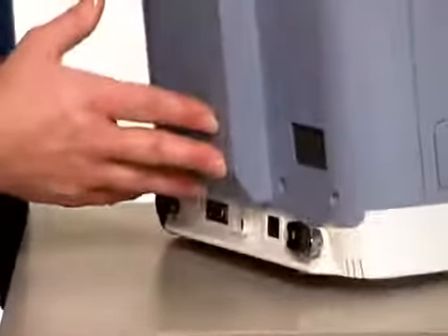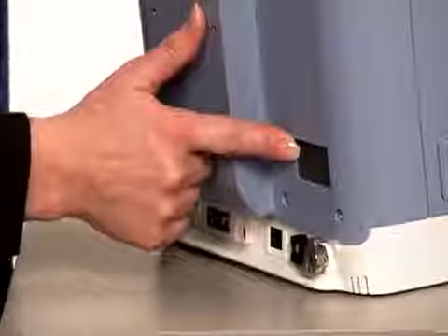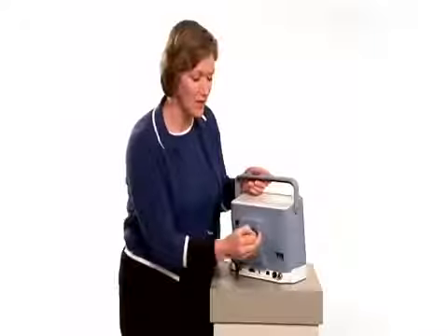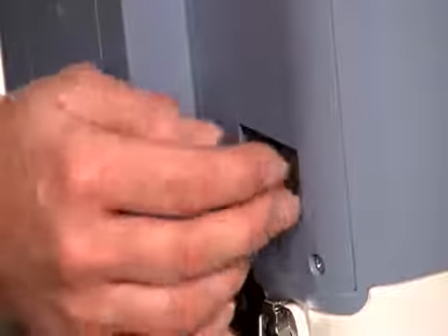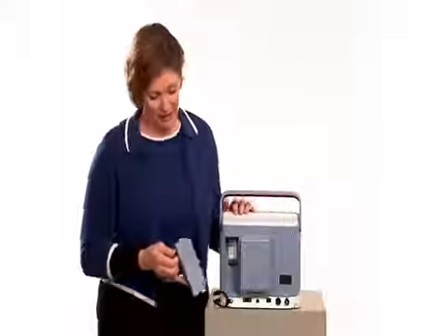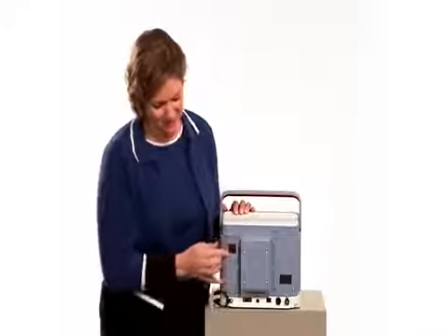On the back of the Trilogy, you'll see an air inlet which holds a gray foam filter. The filter, which screens out normal household dust and pollen, is washable and reusable. You must have the filter in place when the device is operating. On the other side of the ventilator is a detachable battery pack slot. A lithium-ion detachable battery pack is used to power the device and attaches here.